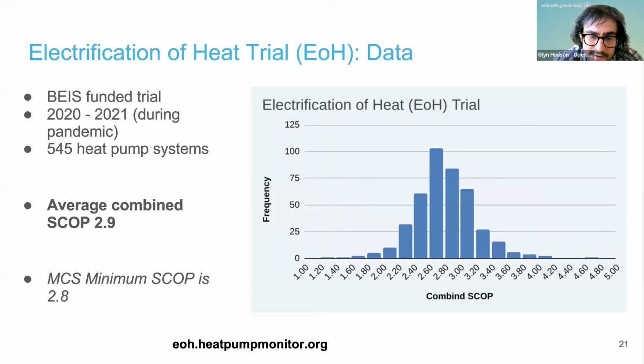Next slide, please, Will. So I'm just going to briefly compare the performance of the heat pumps on HeatPumpMonitor with the performance of the heat pumps from the electrification of heat data, which was the last government trial on heat pump performance. It was a BEIS-funded trial from 2020 to 2021, and they installed a large number of heat pumps with monitoring, 545 systems, and the average SCOP of these systems was 2.9, which is above the MCS minimum of 2.8.